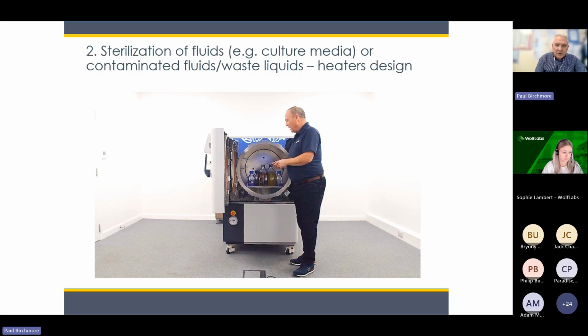Just to emphasize something Neil touched on there, something called air ballast. When you use such a system with these enhancements, which has a cooling jacket, that's a very quick way of bringing the media in the bottles down in temperature. In some ways, the cooling jacket can be too efficient. It can bring the temperature and the pressure down very quickly. And the reduction in pressure could give rise to reducing the boiling point of the media, hence you get a boil over again, which is hazardous and wasteful.